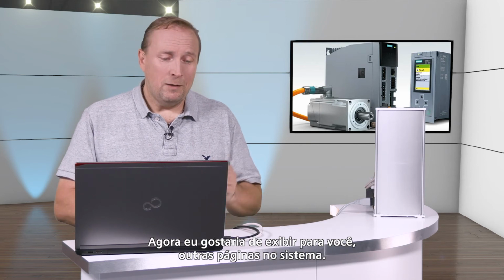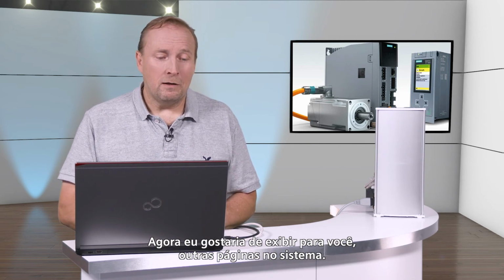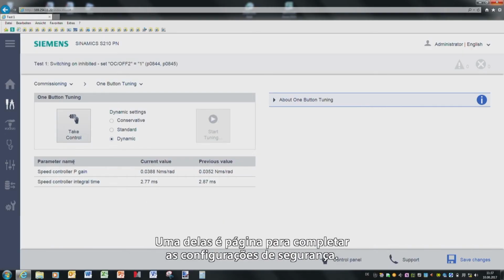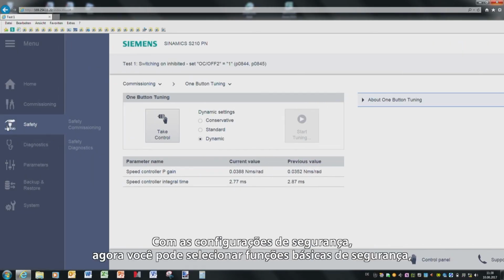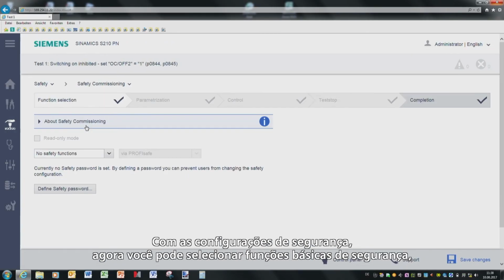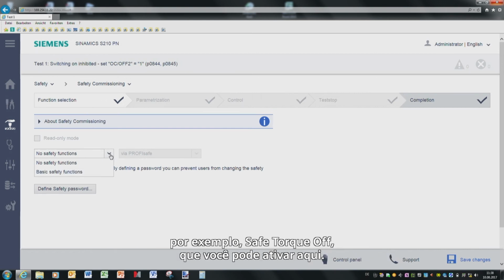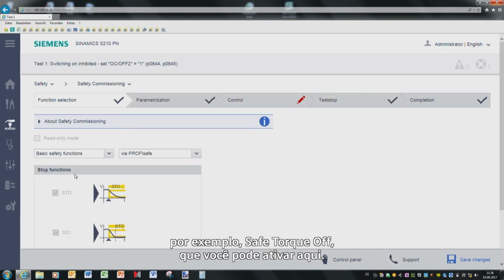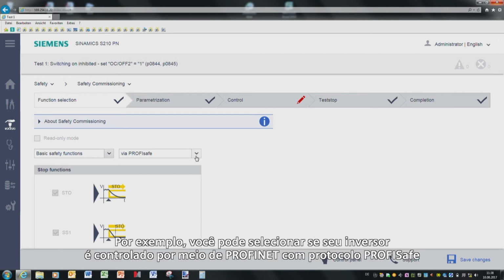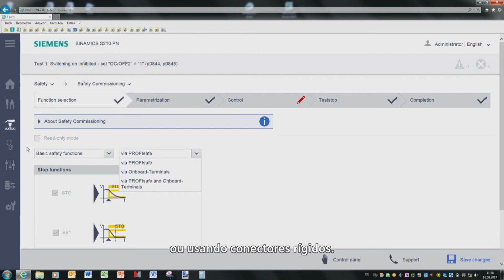I would now like to show you the other web screen forms. One of these is the screen form to complete the safety settings. With the safety settings, you can now select basic safety functions. For example, Safe Torque Off, which you can then activate here. For example, you can select whether your drive is controlled using PROFINET with the PROFIsafe protocol or using hardwired terminals.